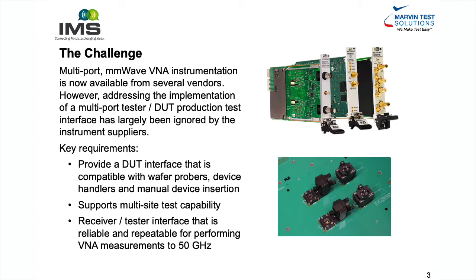Guaranteeing reliable and repeatable mmWave measurements requires careful attention to design details and implementation of the RF transmission path from the RF test resources through the tester interface to the load board and terminating at the DUT socket. Specifically, selection of interface cables, connectors, and the load board design parameters are critical to ensure quality and repeatable test results.